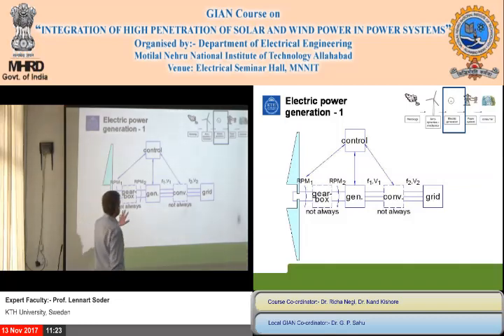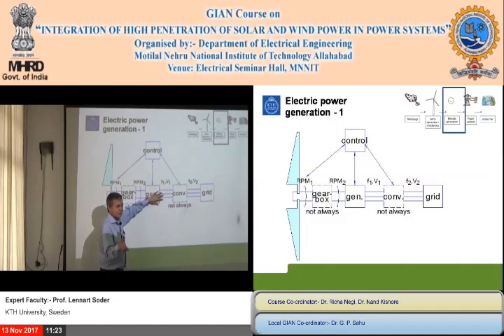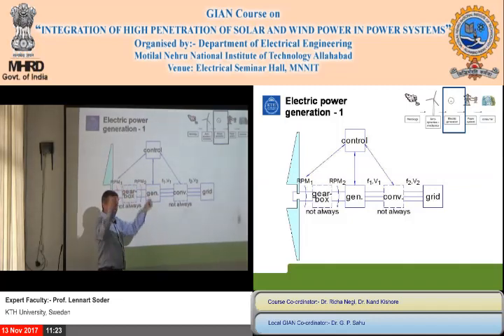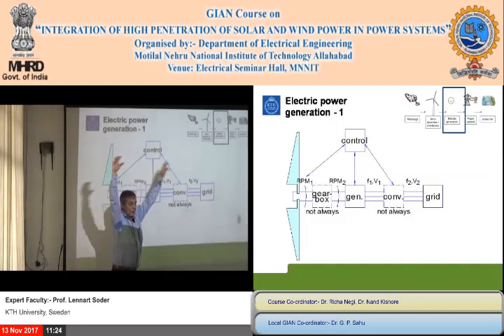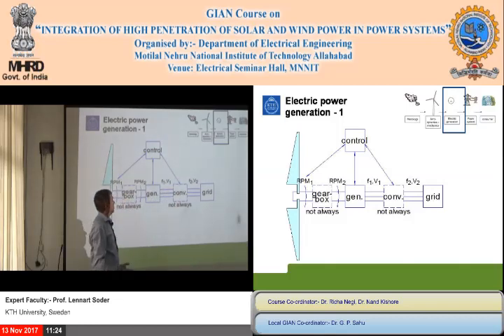Anyhow, that means a generator, for those who know machines, has to be high speed. You cannot have a machine working this slowly. So you either have many poles in the machine, that's one way, also common in hydropower, or you have a gearbox to let this part move faster, much faster than in reality. So you have many-pole machines, and you can see big generators with many poles, like from Enercon, for example.